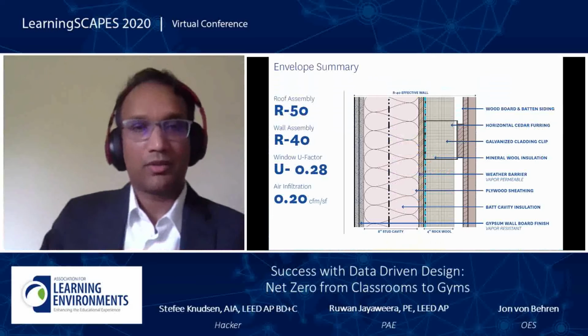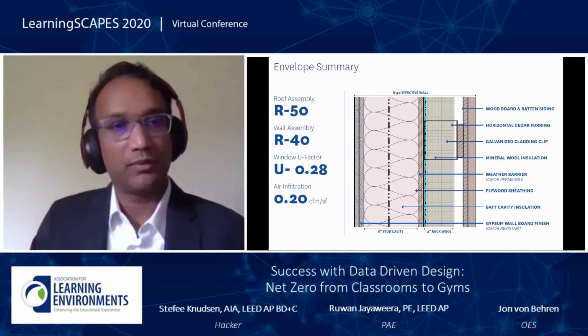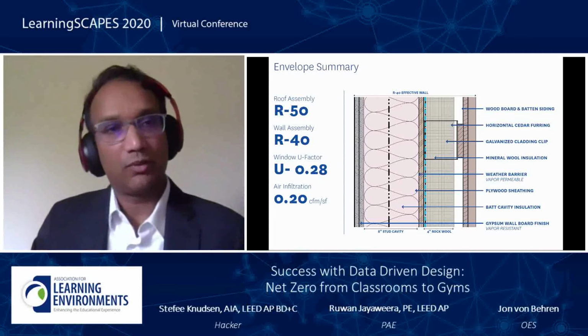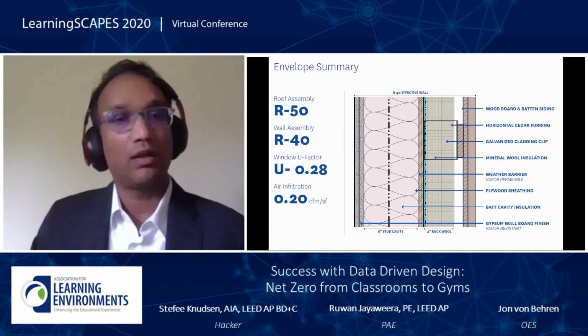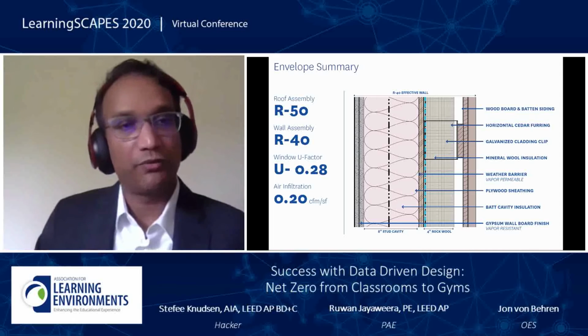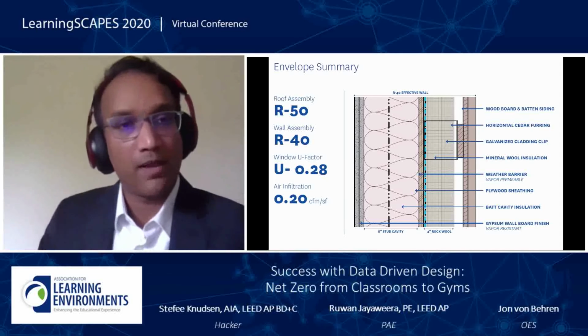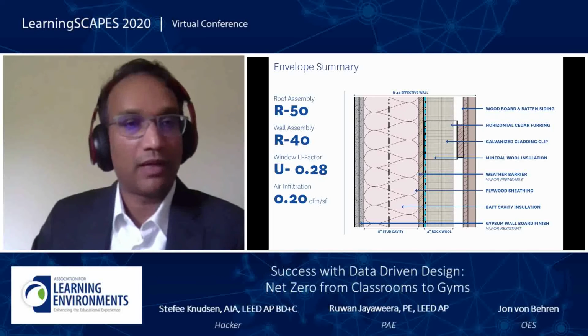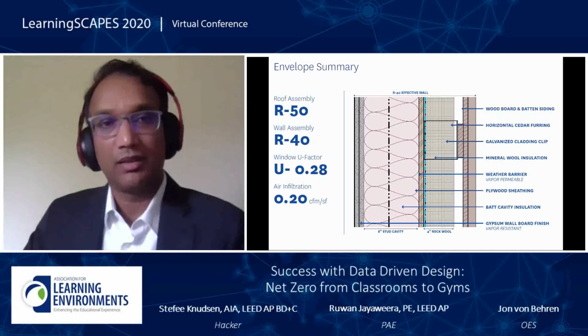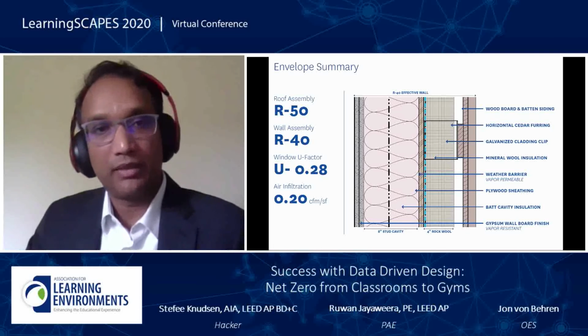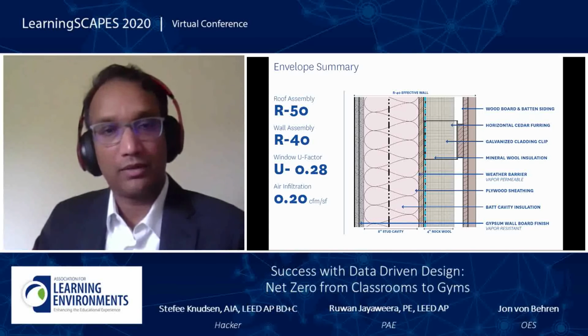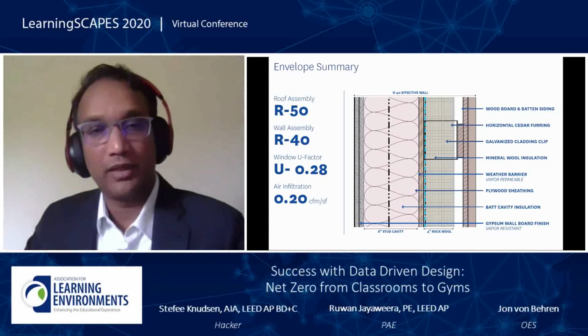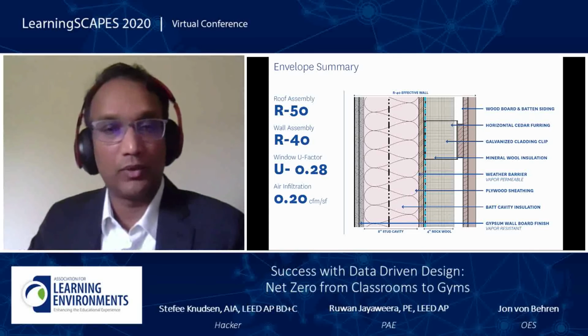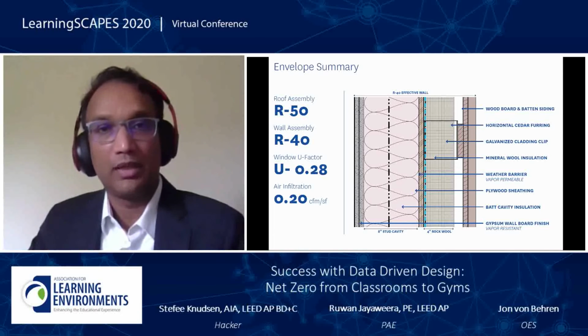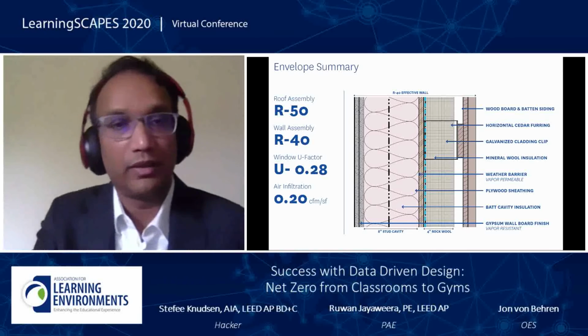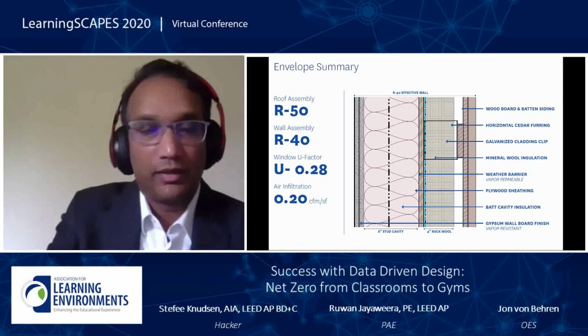Here's the wall construction detail on the lower school: an R40 assembly. This shows the entire envelope: R50 wall, R50 roof, R40 wall, U-0.28 windows, air infiltration of 0.2 CFM per square foot of wall area. We achieved this through double-pane fiberglass frame windows, not triple pane, since we couldn't afford triple pane. We have an 8-inch stud cavity with batt insulation, then a 4-inch layer of continuous rock wool with Z-clips, and a lightweight cladding on the exterior, with the weather barrier in there too.